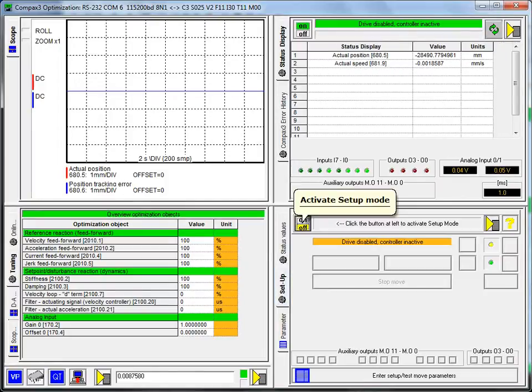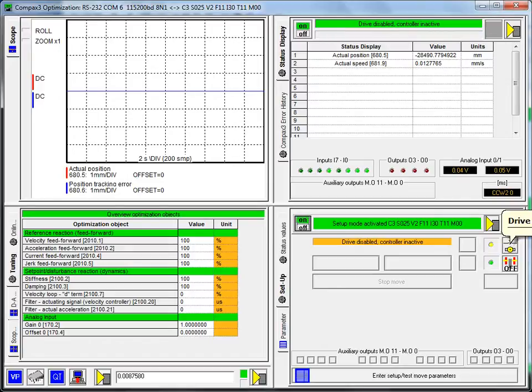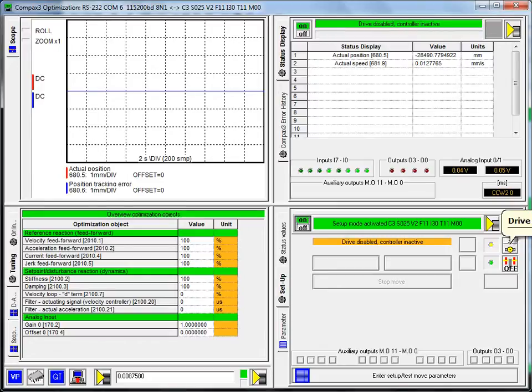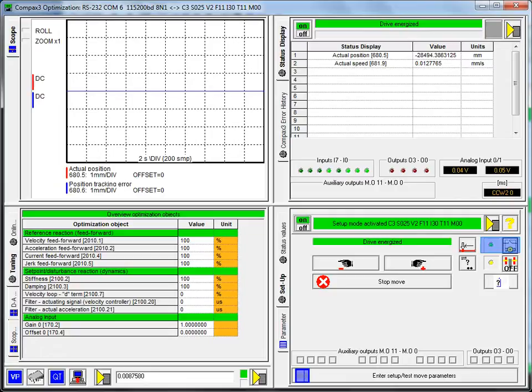In this setup tab on the second tab on the bottom right-hand corner, if you click to activate the setup mode, this will grab control of the Compax 3 through the software. So this isn't looking at the inputs and the outputs on the X11 or the X12 or the optional X22 connector. It's not looking at the code assist program if you're using a T30 or T40. We are strictly running this control here locally, not looking at any of the field bus options either. When you first enable the drive, it will automatically deactivate the brake. So you don't need to click that.